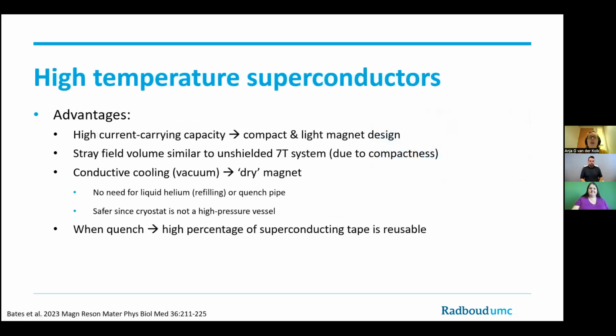So there are several advantages of a high temperature superconductor. For one, it has a high current carrying capacity. So you can put a lot of current through the wire. It's actually not a wire, it's a tape. But you can put a high current through it, which also means that it can be compact and a light magnet design. So it doesn't have to be this huge, enormous MRI scanner where you need half a city to put it. It can be almost as small as the 7T or the 3T. And then it has a stray field volume that is similar to unshielded 7T systems, which of course is very important when you think about the whole construction of your machine room and the area around it.